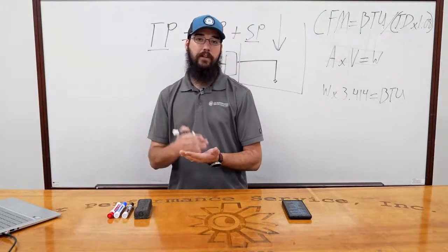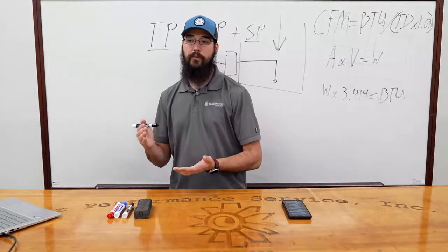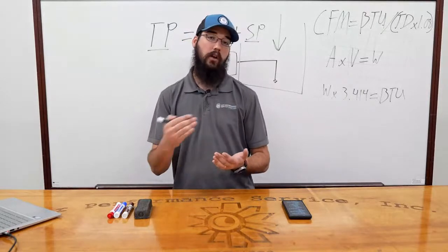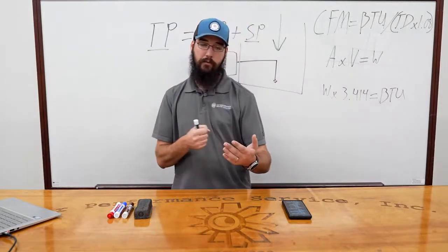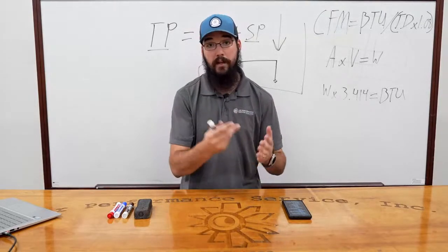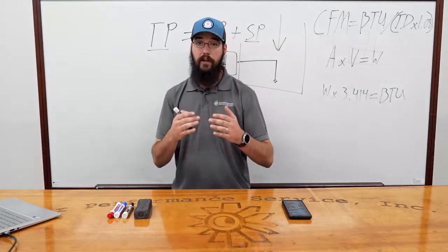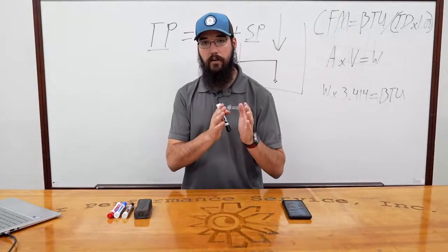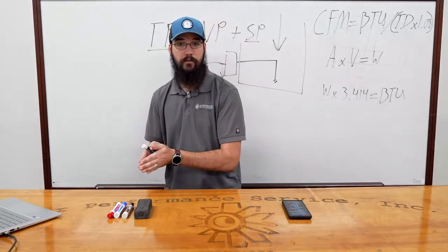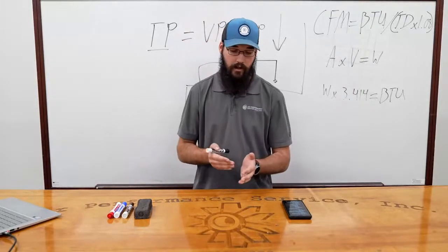So if that TXV is rated at, say, 10 tons, 30% of that is how low it can go and hold that refrigerant back without losing control of the superheat. Meaning, in a low airflow scenario, you would end up flooding. So yes, you could walk up with a low airflow condition causing a low saturation, let's say 35, 34 degrees, maybe even lower Fahrenheit.